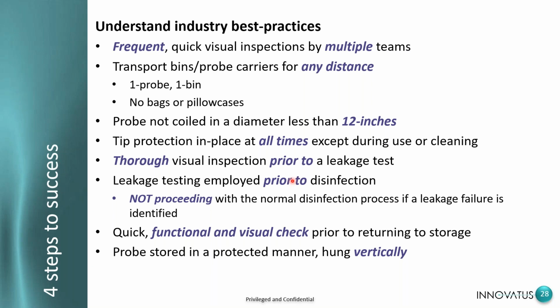A quick functional and visual check prior to returning to storage. So when you bring it back to storage, take another look at it, make sure there are no breaches. And then the probe is stored in a protected manner, hung vertically. We want these probes hung vertically and laid out where the insertion tube is flat.